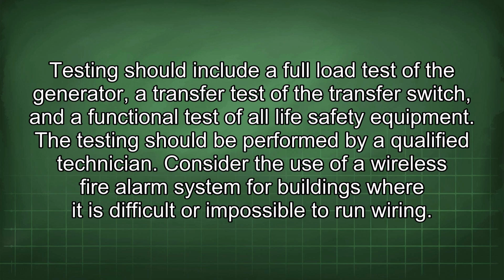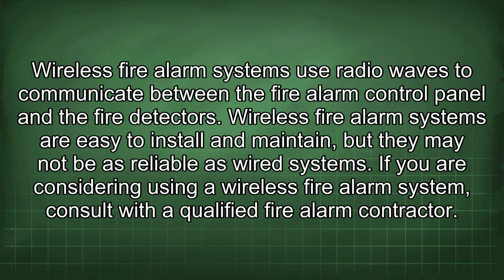Consider the use of a wireless fire alarm system for buildings where it is difficult or impossible to run wiring. Wireless fire alarm systems use radio waves to communicate between the fire alarm control panel and the fire detectors. Wireless fire alarm systems are easy to install and maintain, but they may not be as reliable as wired systems. If you are considering using a wireless fire alarm system, consult with a qualified fire alarm contractor.